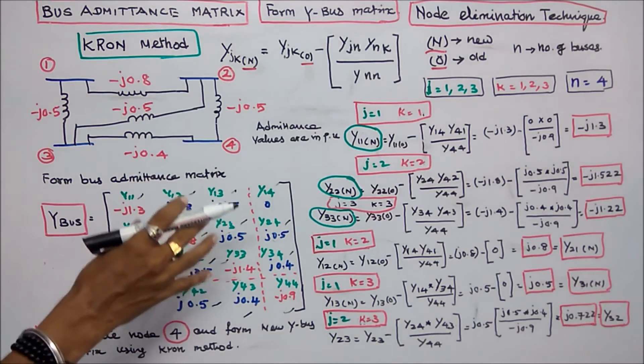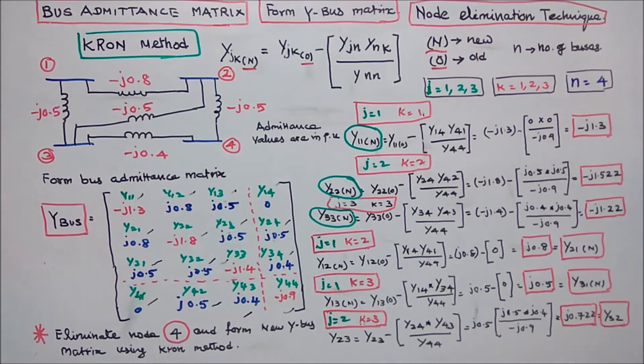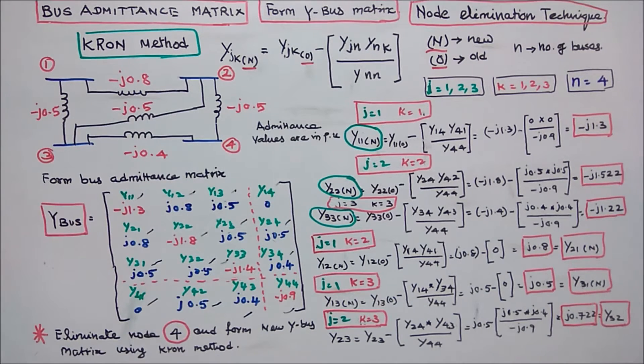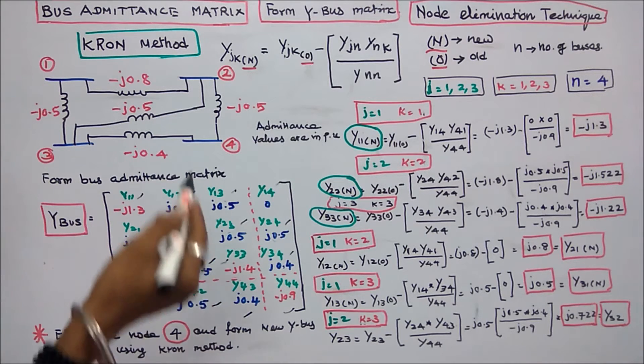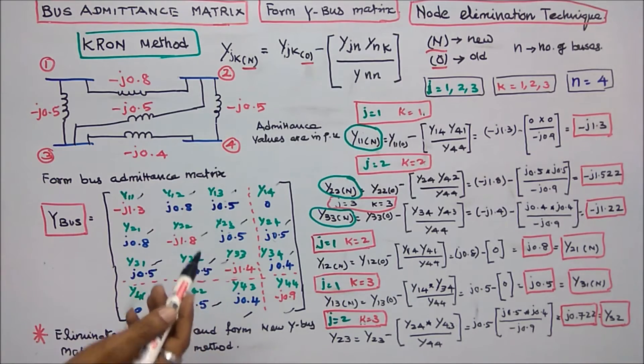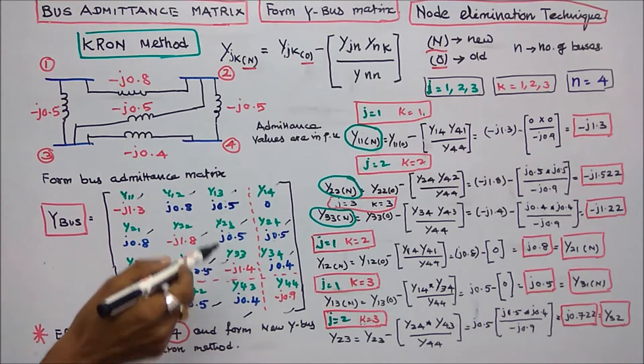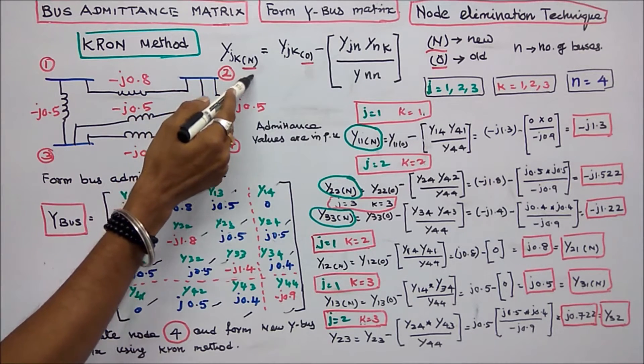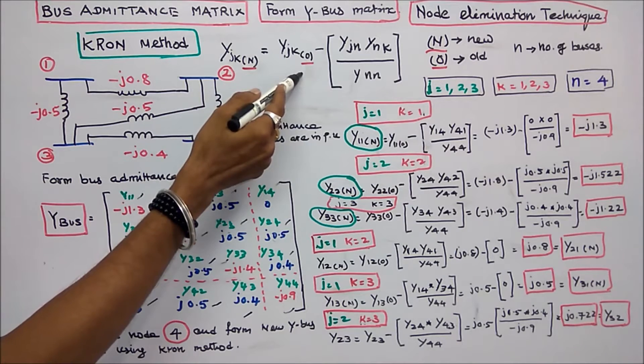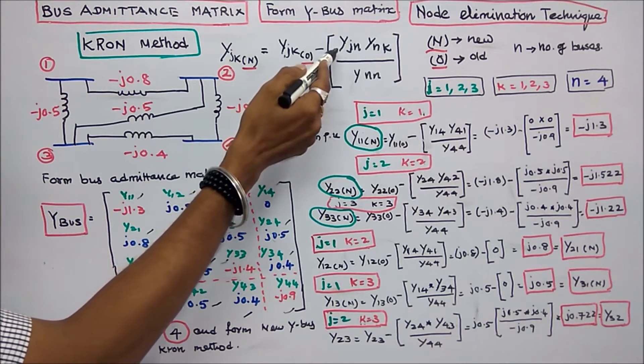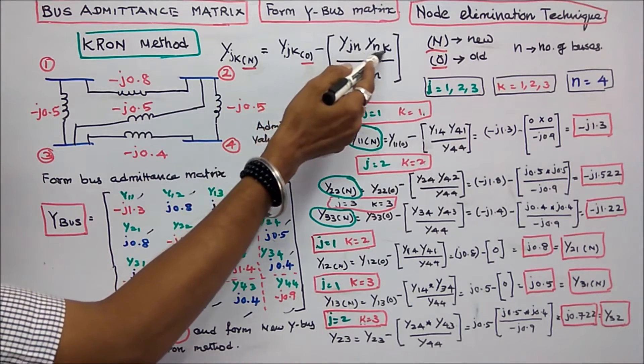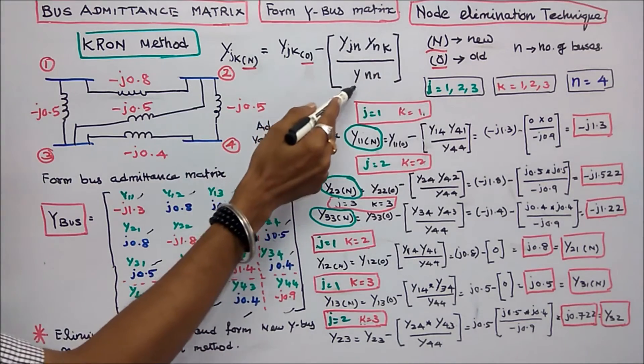This completes the bus admittance matrix for the system. The second question is to eliminate node 4 and form a new Y-bus matrix using Kron's reduction method. If we eliminate node 4, we get a 3×3 matrix. The Kron's method formula is: Y_JK(new) = Y_JK(old) minus Y_JN times Y_NK divided by Y_NN.